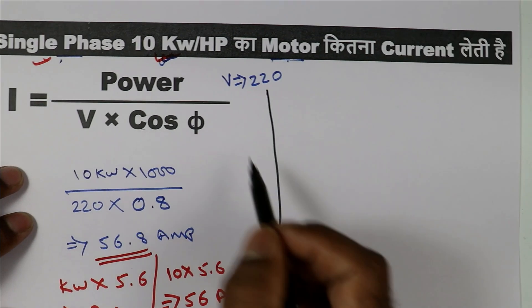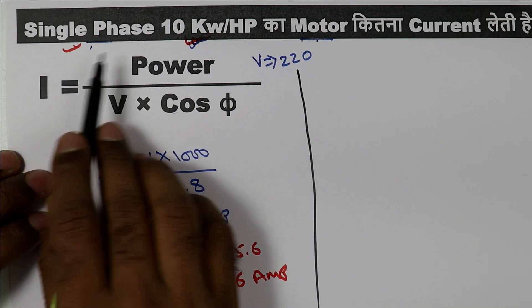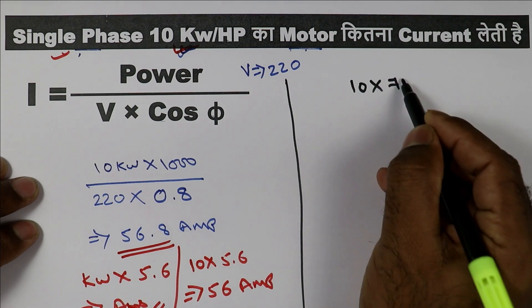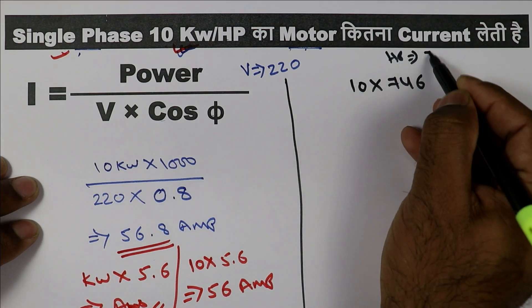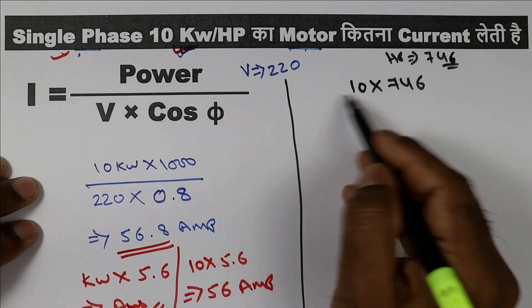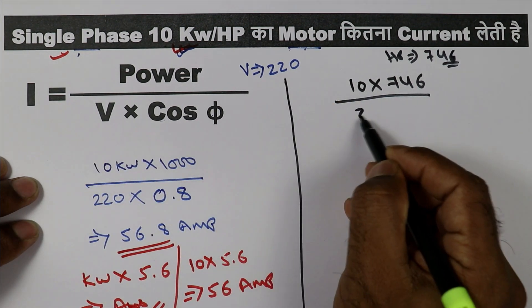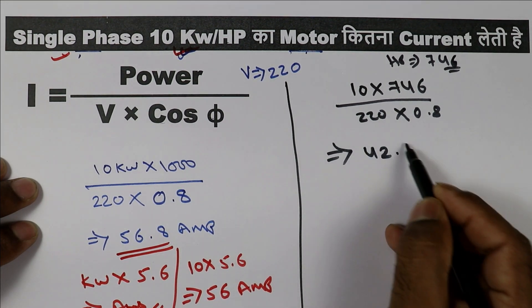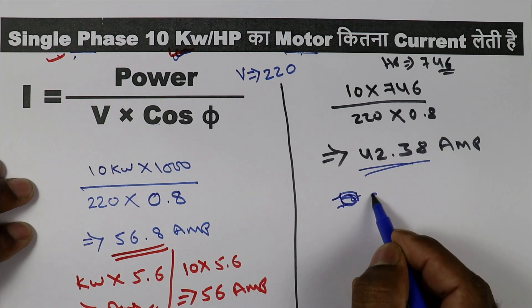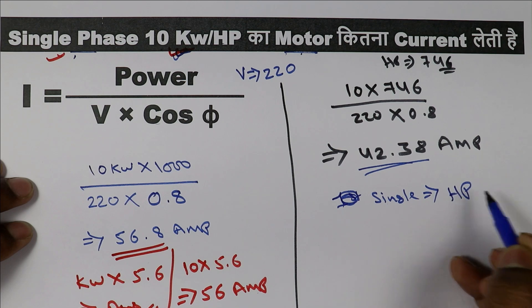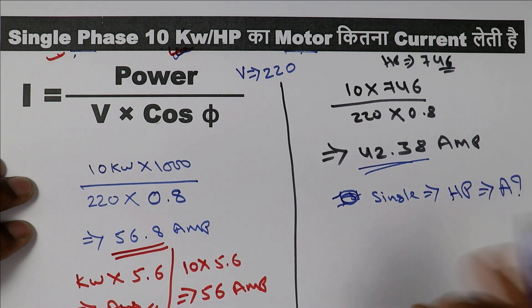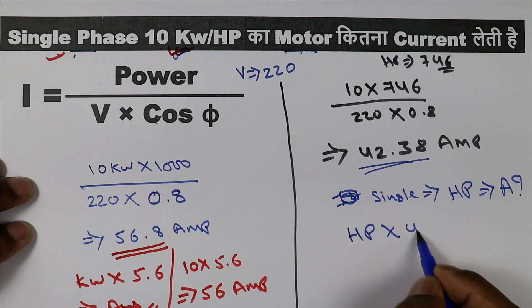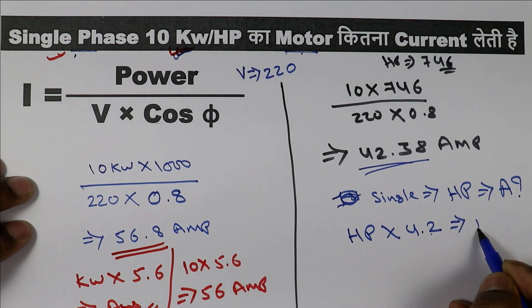Now for a 10 horsepower single-phase motor, we use the same single-phase formula. Multiply 10 by 746 to convert horsepower to watts, divide by voltage (220V) times power factor (0.8). When we solve this, we get 42.38 ampere. That is the current rating of a 10 HP single-phase motor.